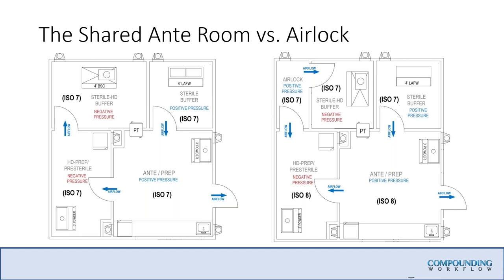So I'm actually going to add an airlock. The airlock — which is not present in Design A but added to the same design as Design B — essentially allows me to break up the spaces. This area where the depyro oven is, hand hygiene, and high-risk weighing can now be rated as ISO 8, so environmental sampling isn't as intensive. And I'm doing the HD prep separately — weighing testosterone or any other dry API before going to final filtering or terminal sterilization — just by breaking up two ISO spaces with that airlock.